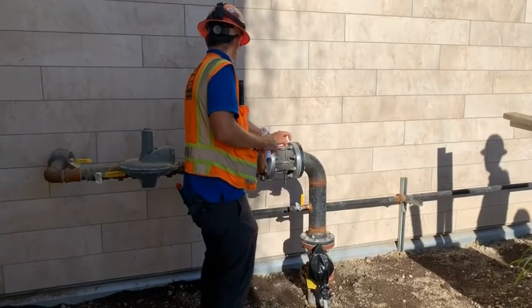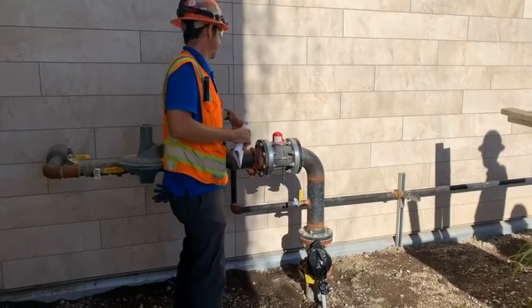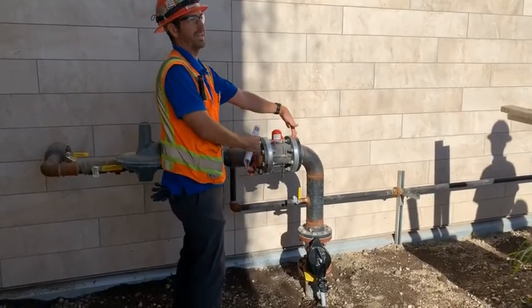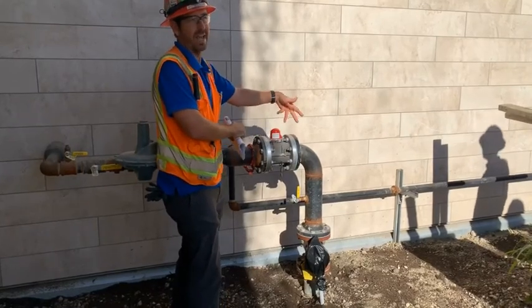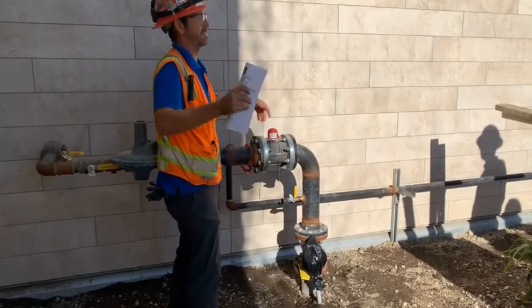So we have the earthquake valve. Just downstream of the earthquake valve, you'll see this pipe right here. We're still medium pressure gas right here. Right now it's roughly 7.5 PSI. It'll fluctuate depending on the campus loop.